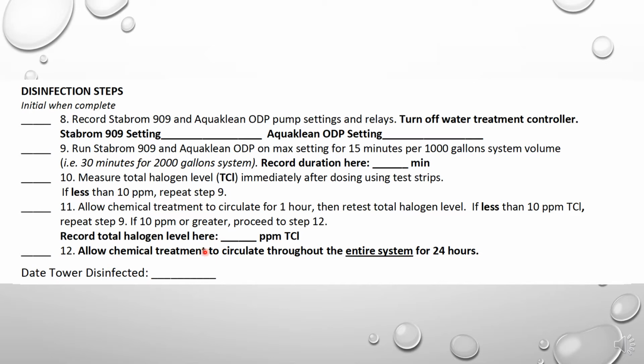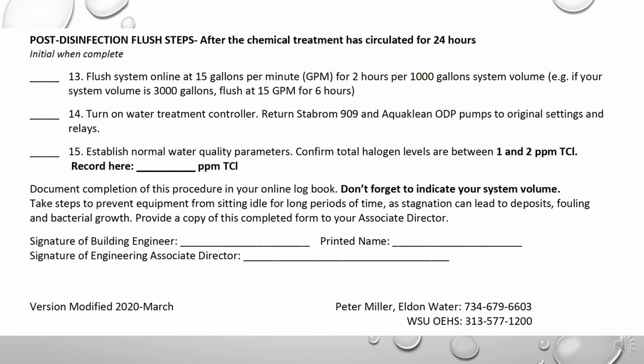And once you get up past 10 parts per million, you want to allow that chemical to circulate throughout the entire system, so all your pumps, all your heat exchangers, for 24 hours. And then you just indicate the date that you disinfected your tower. Finally, after that disinfection, you need to flush your system, so you're going to flush the system online at 15 gallons per minute for 2 hours per 1,000 gallons.